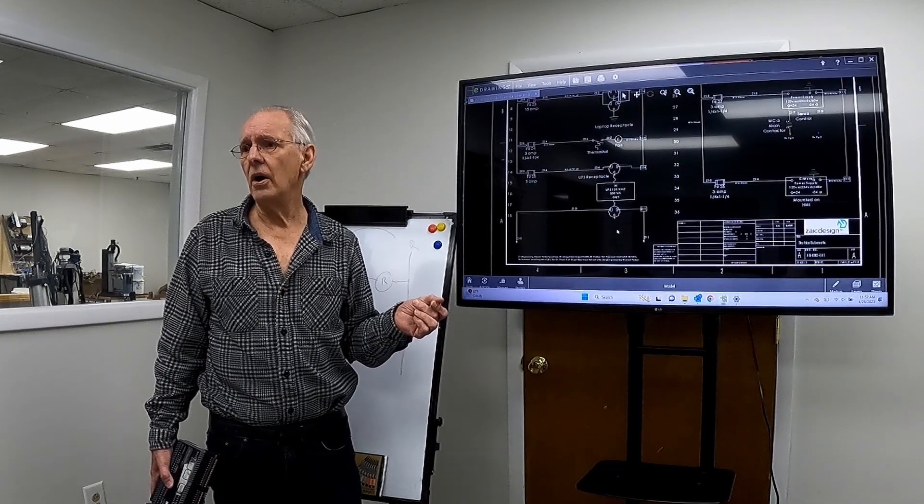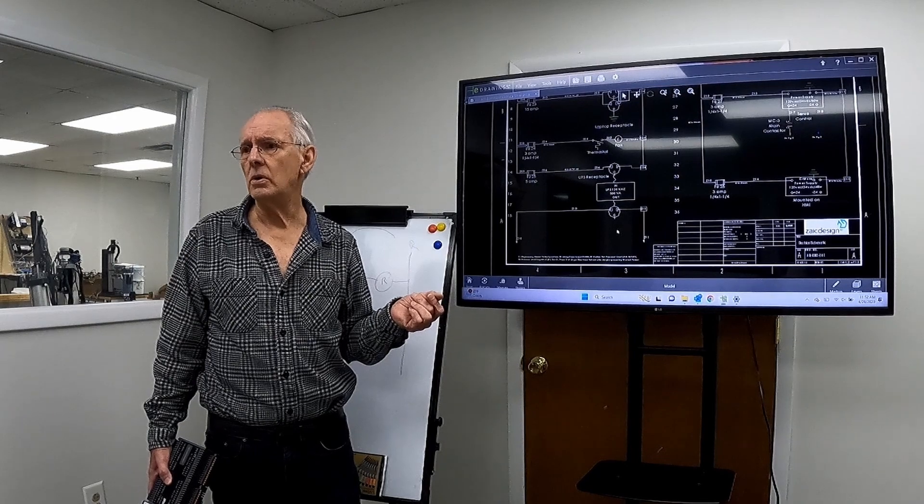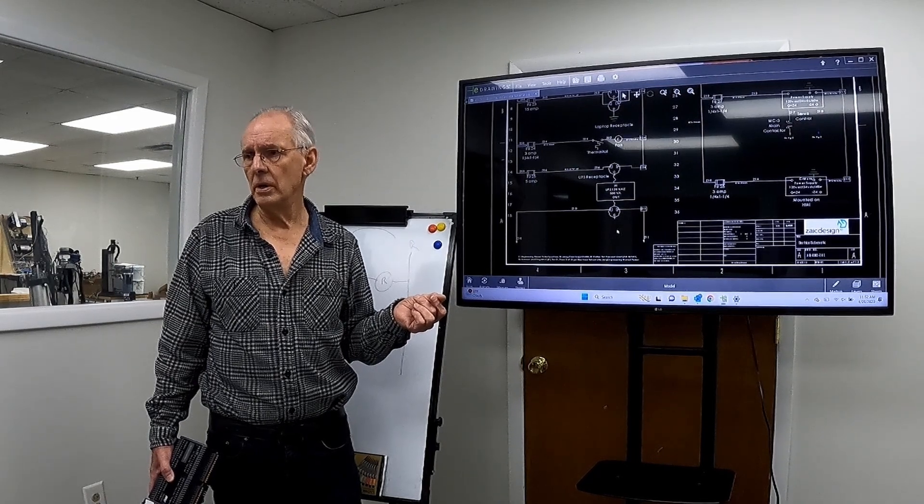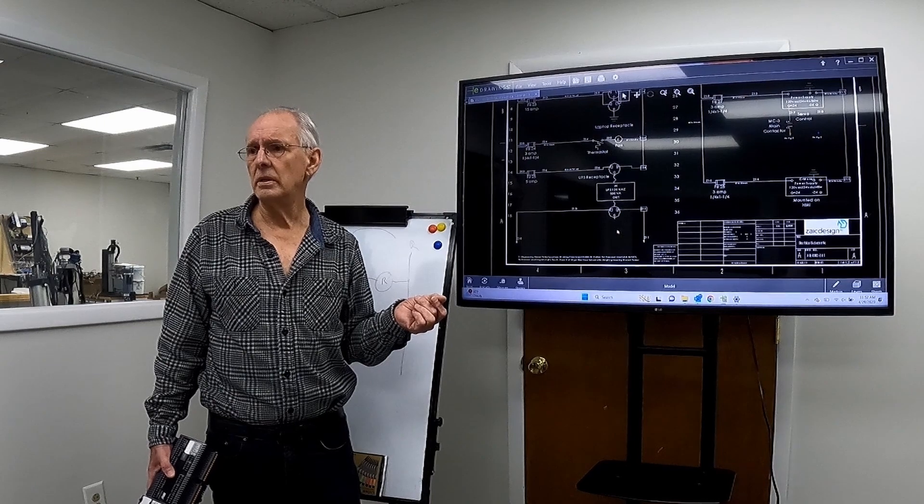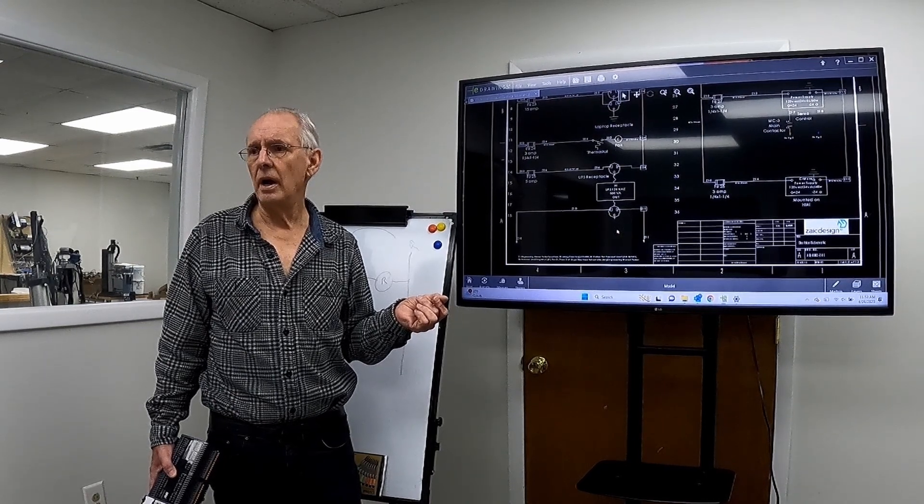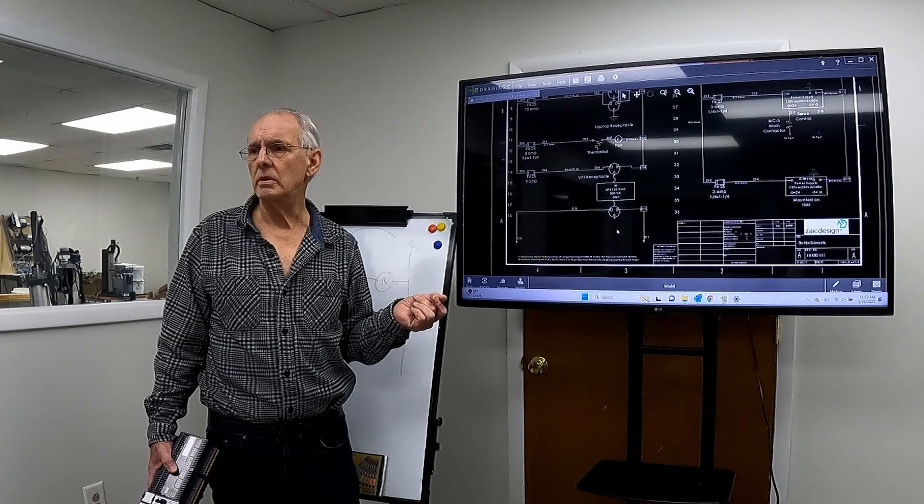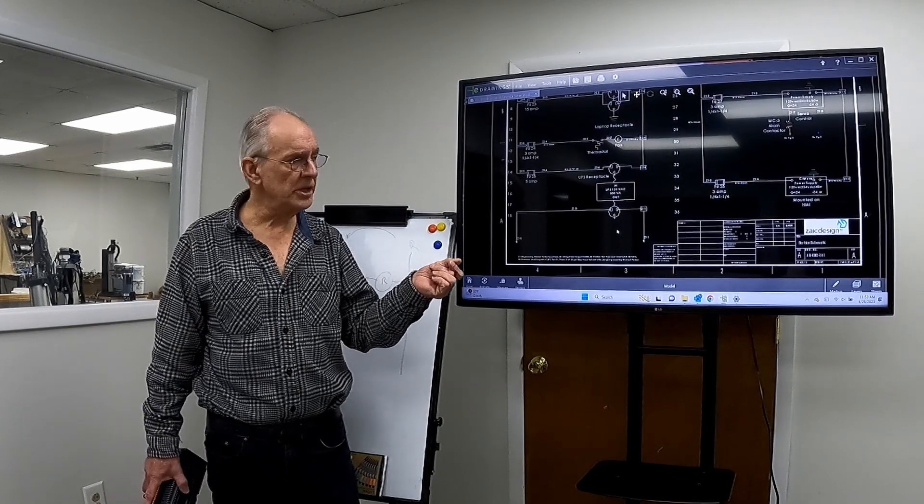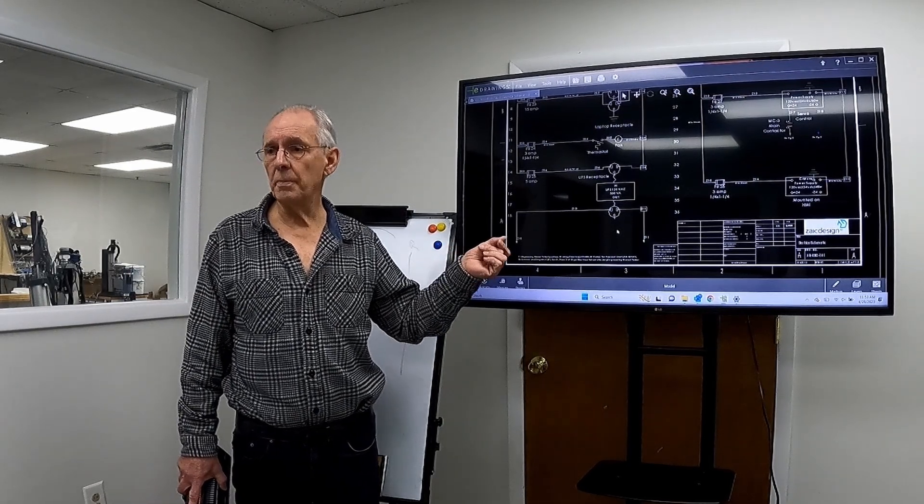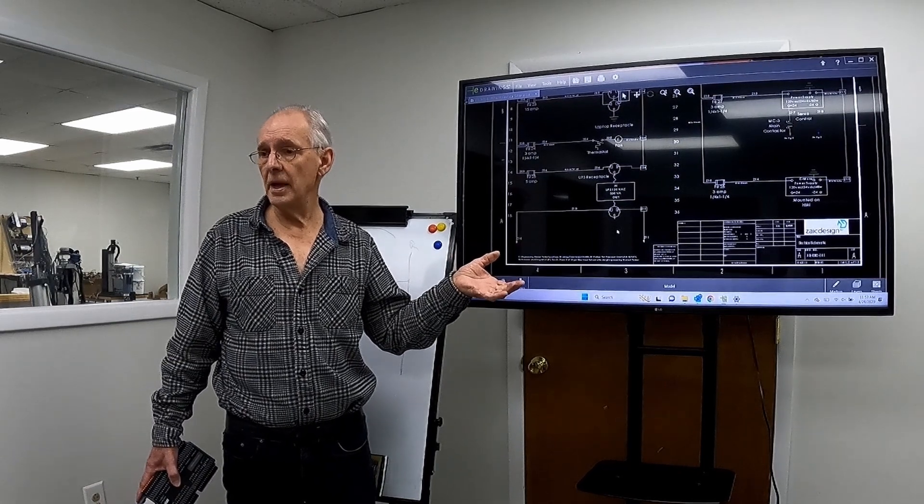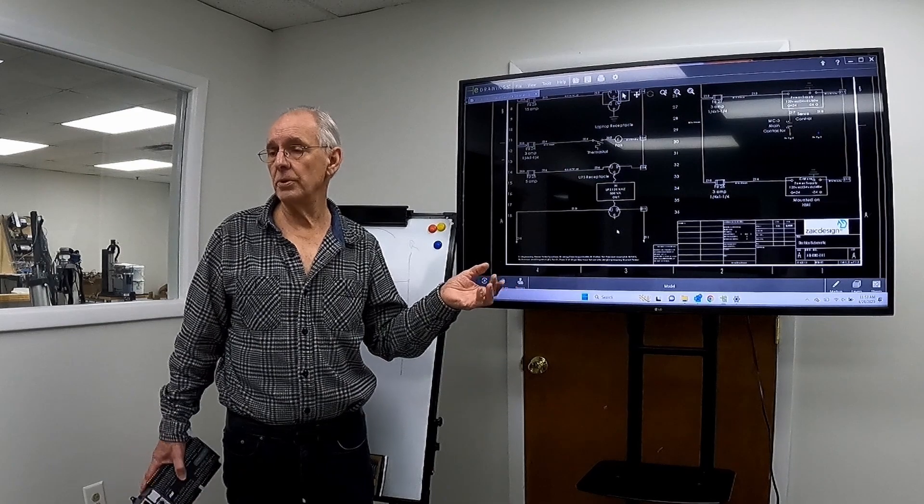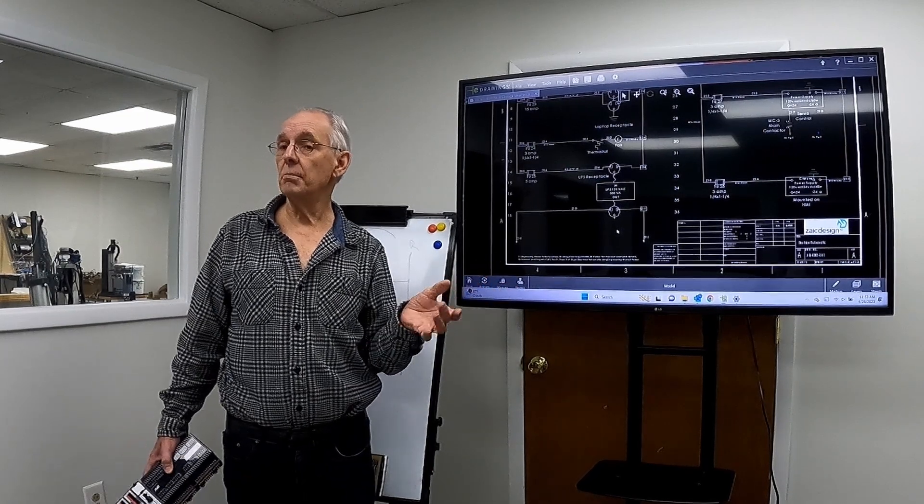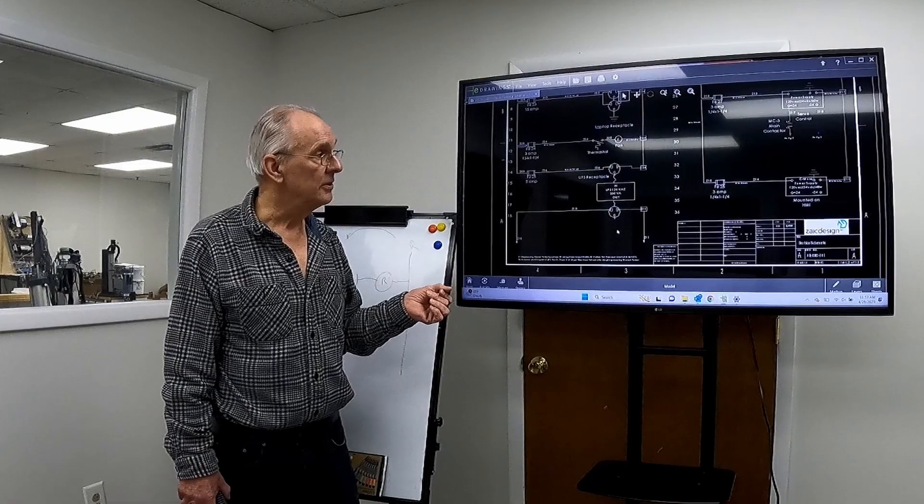So the UPS is primarily providing power to the PLC? Only to the PLC. Well, so if there's a power failure, so it's taking in power from the 120 volt system to charge the batteries and the UPS, but the output is just supplying power to the PLC so that it knows where things are, even though there's no power to the motors and all that stuff. Right, right. So the PLC itself is aware that there's a power failure, and it can then do something about it. It can make sure that - well, it can monitor what's going on, is the idea.